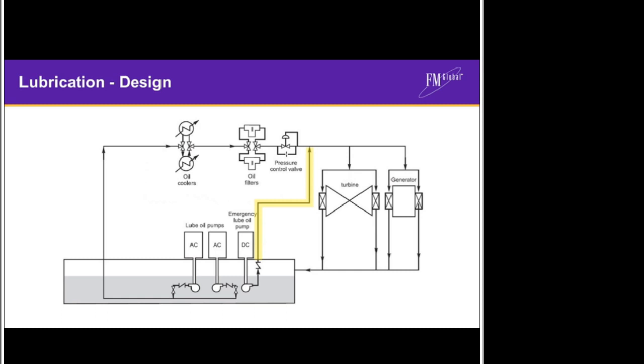In addition to this, turbine operators should pay careful attention to the electrical supply of that DC system. Are there any single points of failure? Are there protection devices on those electrical pumps that ought not to be there? It is common to find thermal overload protection on DC emergency lube oil motors. These single points of failure should also be removed to maximize the resilience of the emergency lube oil supply.